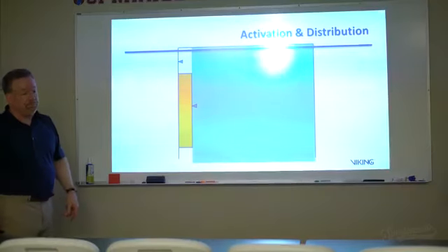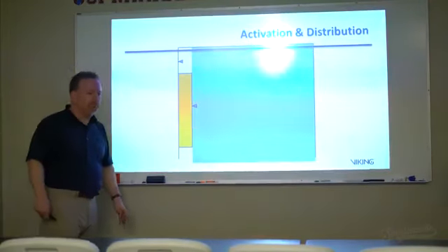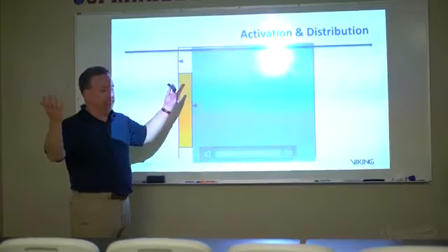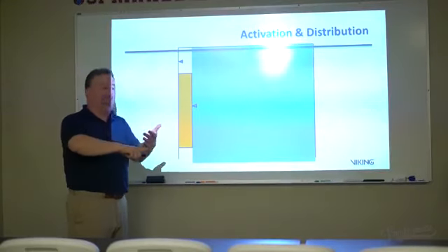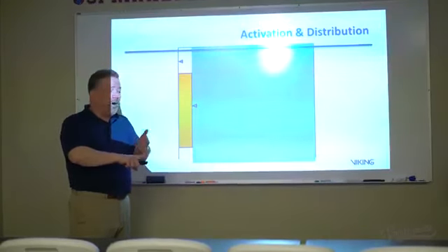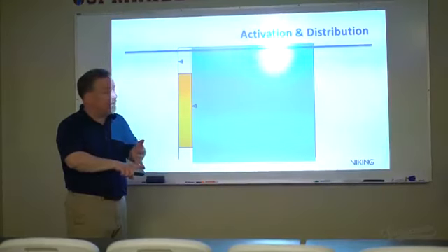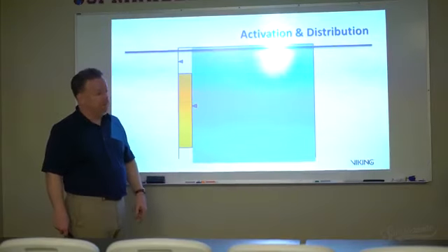Same thing if you have a small room or a certain size room, if it's under that square footage, you would have a room with a door that wouldn't be sprinklered anyway. So if I have a small space, a closet in a hospital, small closets in hospitals don't have to, small bathrooms in certain occupancies don't have to. We're saying you don't even have to put sprinklers in. That's where that small window comes in.